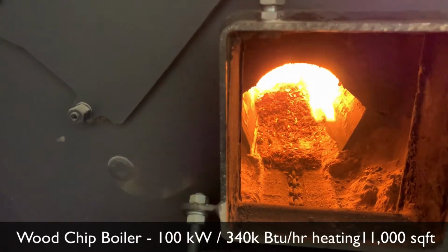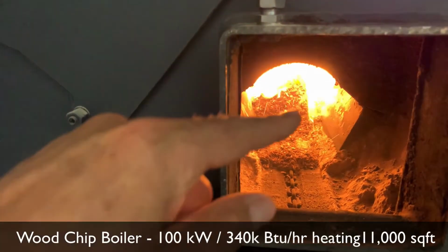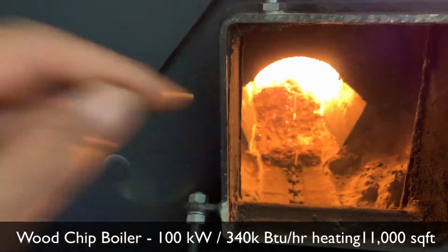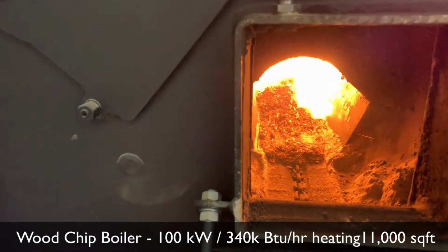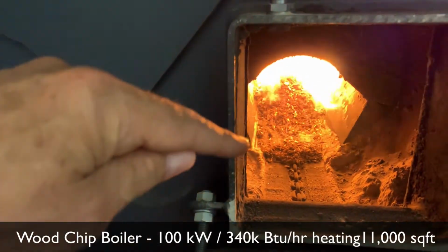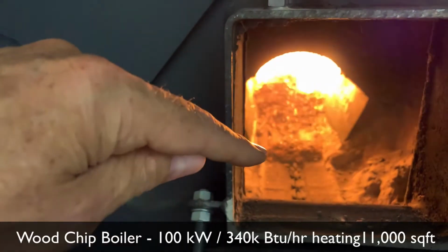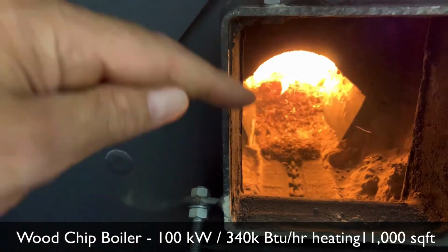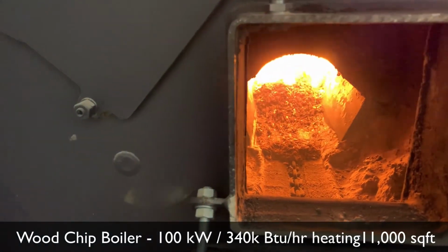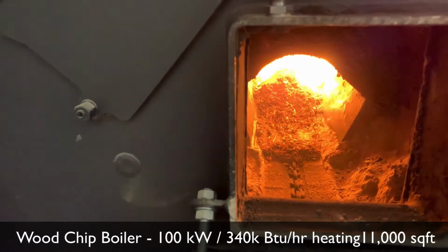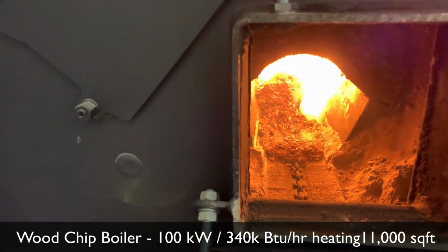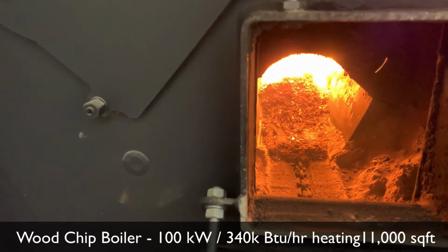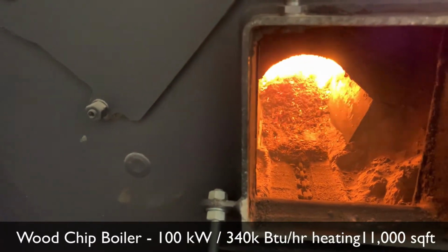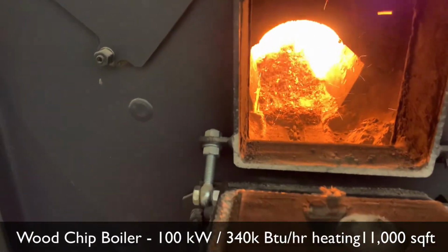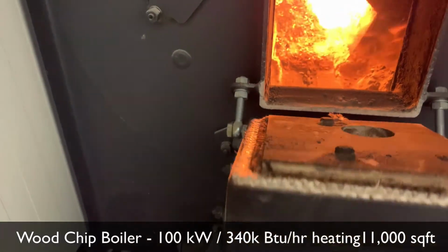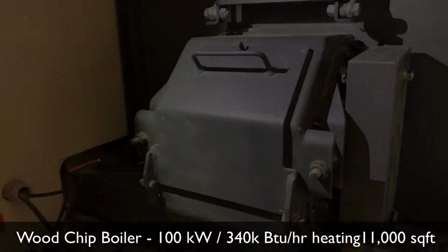So this is a good shot of the fire chamber. You can see on the sides of the fire chamber here, these are the holes where the secondary air is supplied. Along the bottom of the chamber you can see the chain and these little paddles here that are covered in ash. That's the de-ashing system, so that draws the fire bed along the fire chamber section, and then as the ash turns into a nice light grey dust, it deposits it into the auger system, which is at the back of the boiler here.